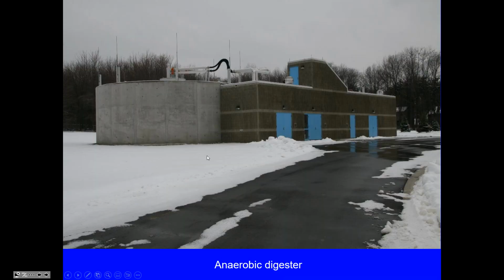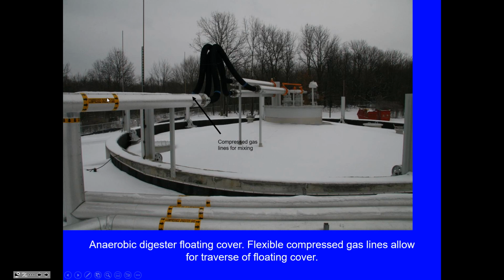So here are a couple of pictures of anaerobic digesters, and ironically, if you look at this one, it's just bare concrete. And I don't know if it's maybe insulated on the inside rather than the outside. That may be the case, that it's concrete on the outside, but hopefully it's insulated somehow, because we just went through the calculations and showed what a waste it is to have uninsulated concrete. But this shows you the challenges that they face of having a cover that's going to be rising and falling. Let me dim the lights, so this is a little bit easier for you to see.